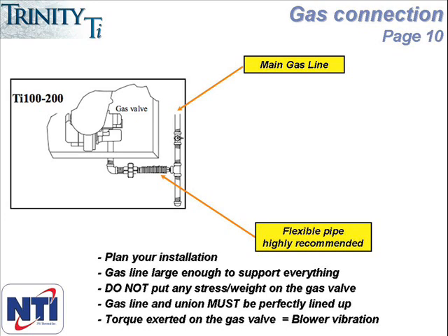and it will depend on things like the total length of the pipe, the number of fittings, the type of gas being used, and the number and BTU capacity of all the appliances in the house. The gas pipe needs to be large enough to properly service all the appliances in the home, and there shouldn't be a noticeable drop in line pressure or manifold pressure when any appliance or combination of appliances lights or is running.